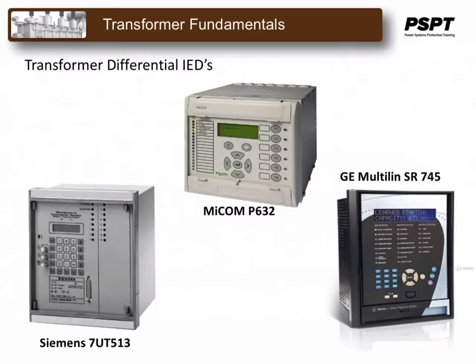Transformer differential protection relays in use today are more advanced and usually part of a multifunctional relay, so they are often referred to as transformer management relays. The relays are microprocessor based and are commonly referred to as intelligent electronic devices, or IEDs. Examples of these transformer management relays that we'll look at are the GE Multilin SR745, the Siemens 7UT513, and the MiCOM P632.